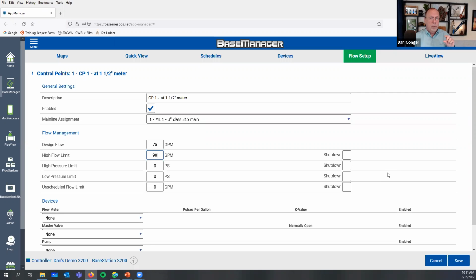Now, assuming it's not a small variation, if it's an enormous variation, well, shutdown then does two things. So what we want to describe is what happens, the way I have it set up with a 90 GPM limit and a shutdown, when we exceed 90 GPM for a sustained period of time? We're going to shut down the master valve. And we get an alert, right? Right. So here without the shutdown, I get an alert. With the shutdown, I get shutdown and an alert.